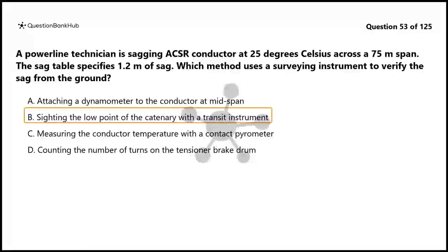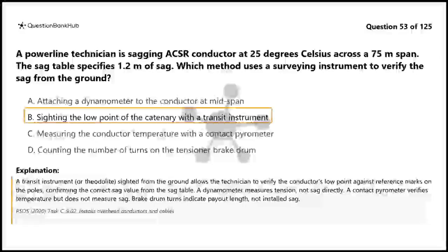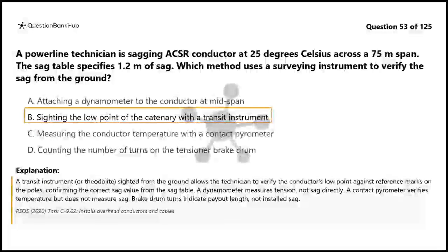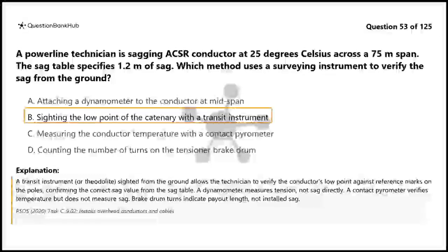The correct answer is B. A transit instrument, or theodolite, sighted from the ground allows the technician to verify the conductor's low point against reference marks on the poles, confirming the correct sag value from the sag table. A dynamometer measures tension, not sag directly. A contact pyrometer verifies temperature but does not measure sag. Brake drum turns indicate payout length, not installed sag.